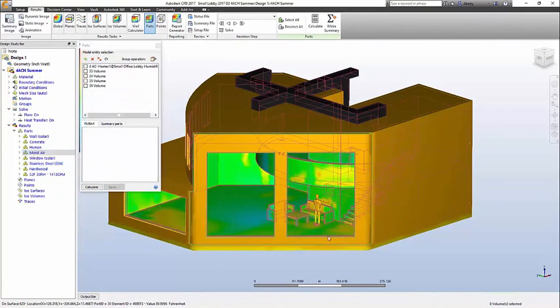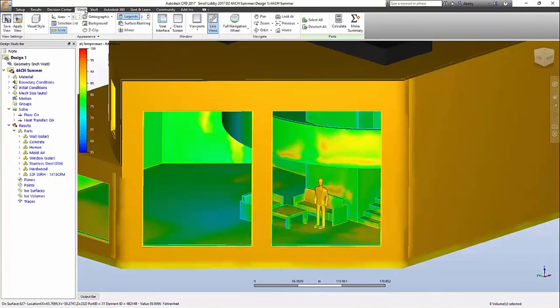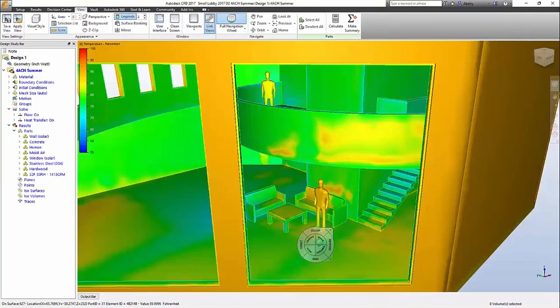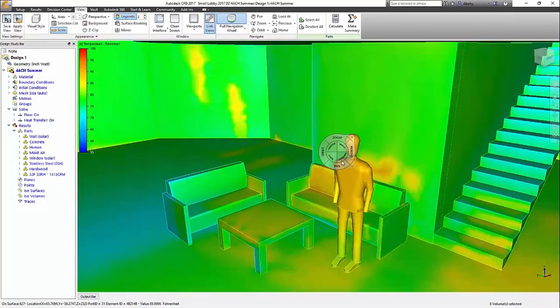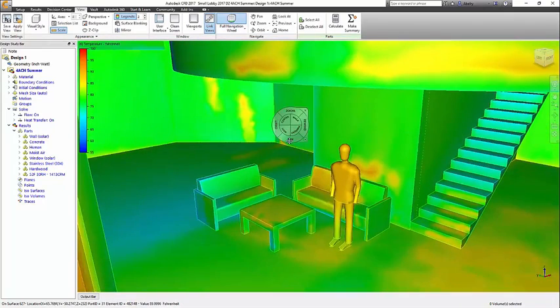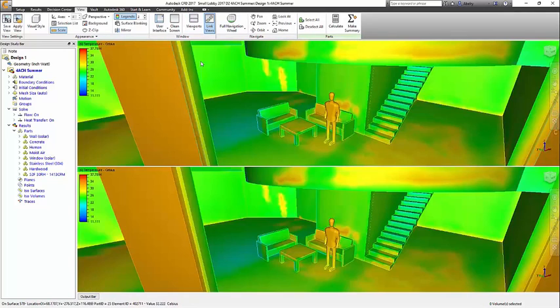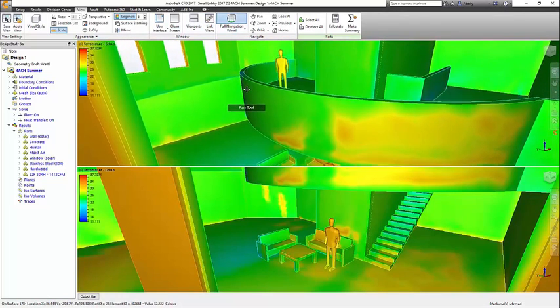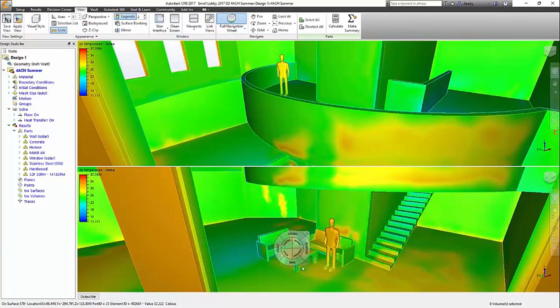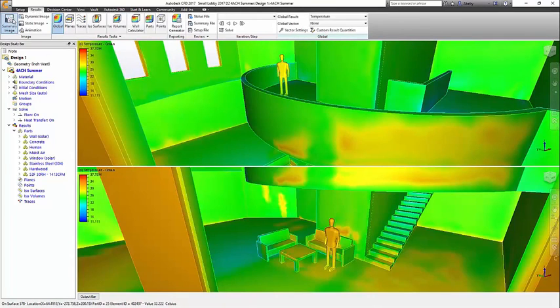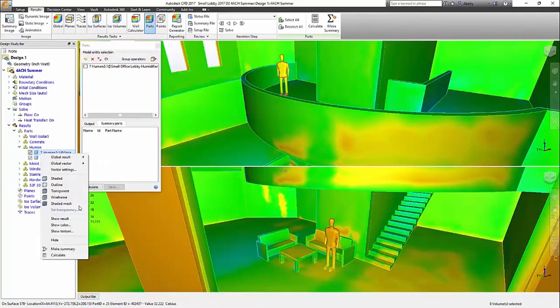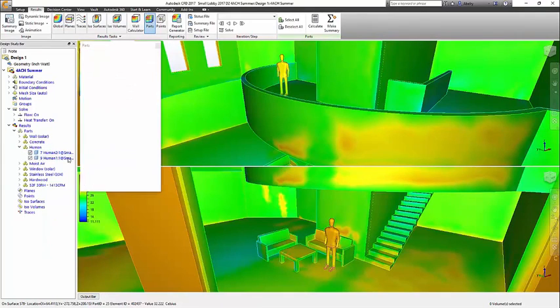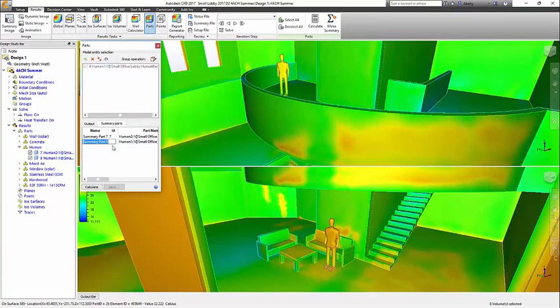Let's start by looking at temperature throughout this room and focus in on the waiting area, and you will see a core body temperature of this person in the 80s and hot areas from the sun coming through the windows and a cold area in the center of the room from the vent that is probably causing too much draft on the sofa. We are just getting started, and I'm already thinking that there's a better vent layout that would provide a more uniform environment in the summer. Let's check in on the person up in the balcony, and you will find that this person is noticeably cooler than the one downstairs.